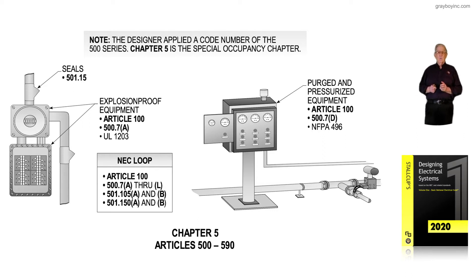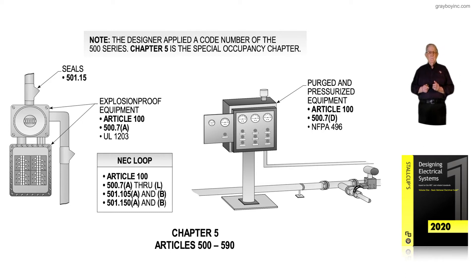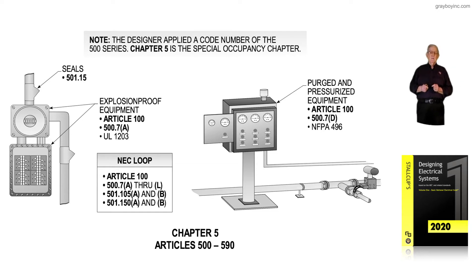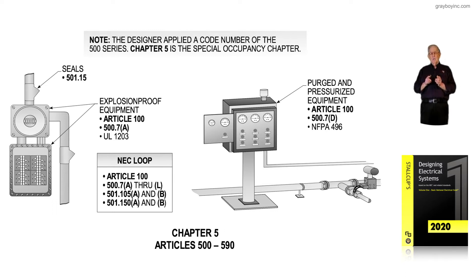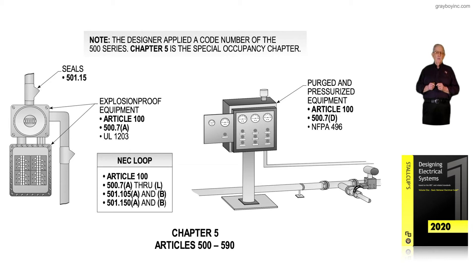Notice we have 501.15 which deals with seals. If we're selecting wiring methods we go to 501.10. If we were selecting special type pieces of equipment we'd go to 501 and through the section dealing with the type of equipment being installed. That's explosion-proof equipment, and the definition is now in Article 100 Part 3. 500.7A deals with protection techniques used in classified locations — explosion-proof equipment — along with UL 1203, which covers much more about explosion-proof equipment.